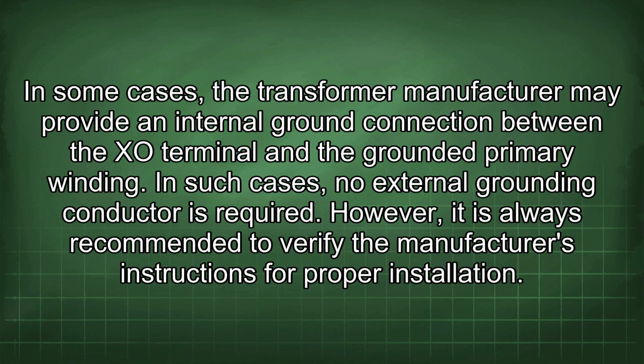In some cases, the transformer manufacturer may provide an internal ground connection between the X0 terminal and the grounded primary winding. In such cases, no external grounding conductor is required. However, it is always recommended to verify the manufacturer's instructions for proper installation.